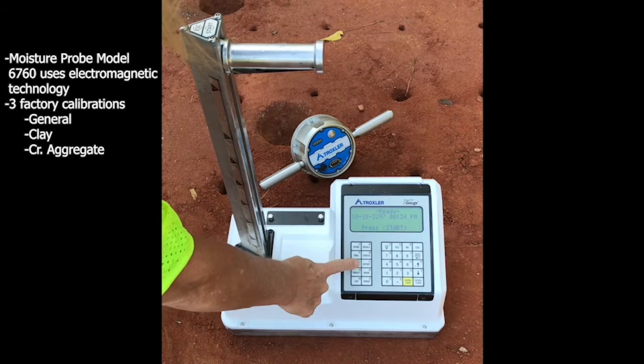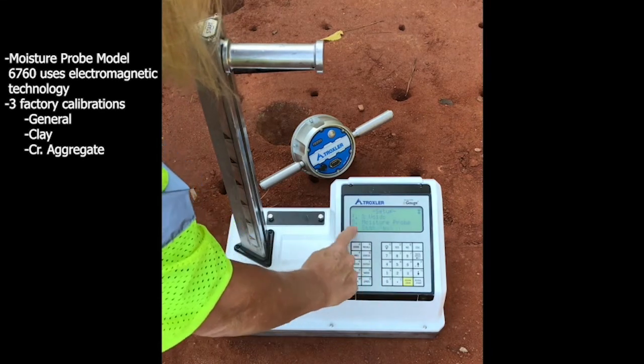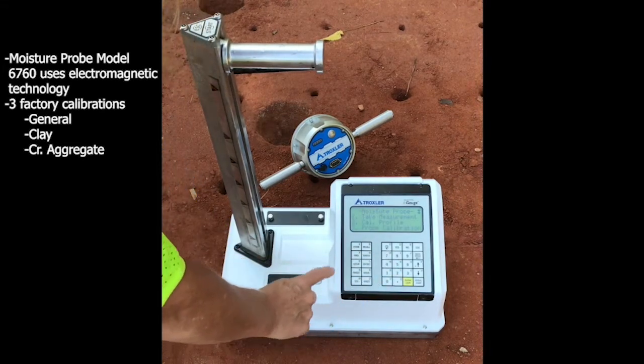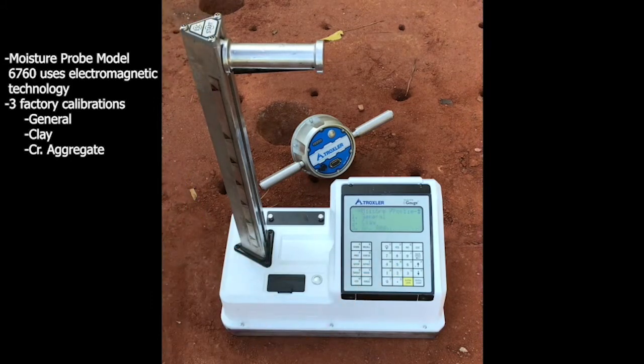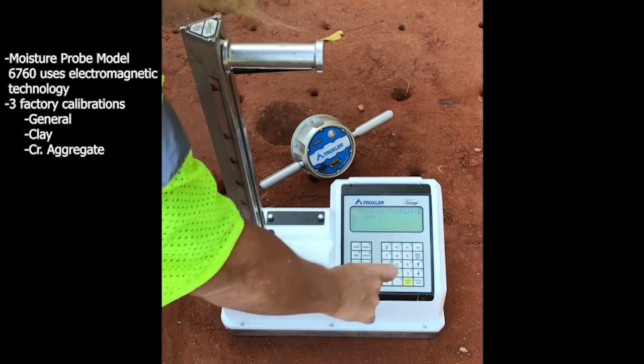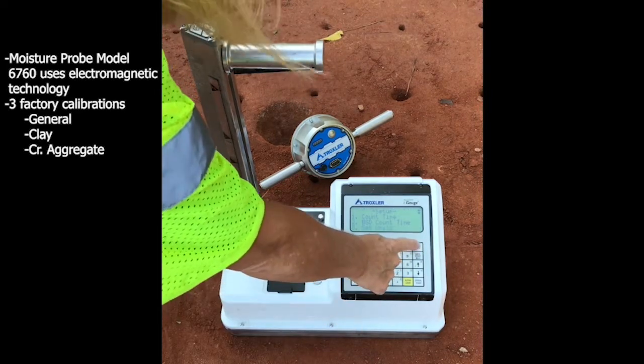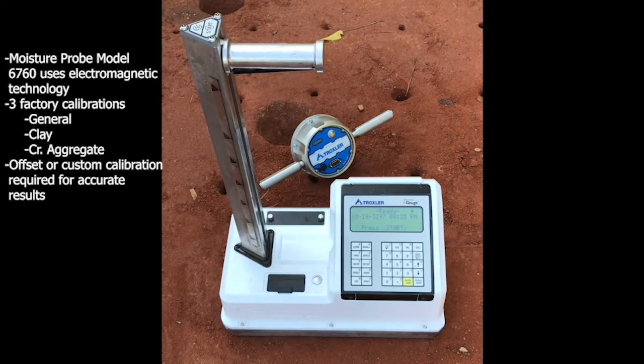This is found in the Setup menu under Option 8, Moisture Probe, and Option 2, Cal Profile. The default is General, number 1, and that is used on most soil types. If you have a very clayey soil, you would use Option 2, and a true crushed aggregate subbase, you would use Option 3. This will get you close to the moisture reading of that material. However, an offset or a probe calibration specific to your soil is needed to get an accurate moisture measurement.